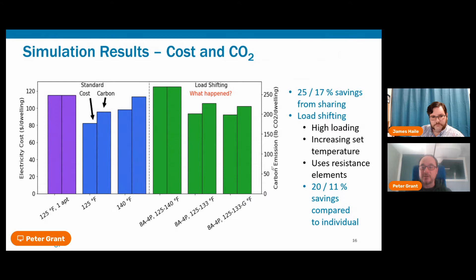So the heat pump can't keep up, and it switches to using the electric resistance elements more often. So yes, we are paying less money per kilowatt hour. And yes, we are emitting less carbon per kilowatt hour. But since we're consuming significantly more kilowatt hours, that overrides all of the benefits. That said, when you look at the actual numbers, switching from individual heat pump water heaters to the shared configuration reduces cost by 25% and carbon by 17%. And then implementing load shifting was still decreasing cost by 20% and decreasing carbon emissions by 11%. So there are still benefits here.